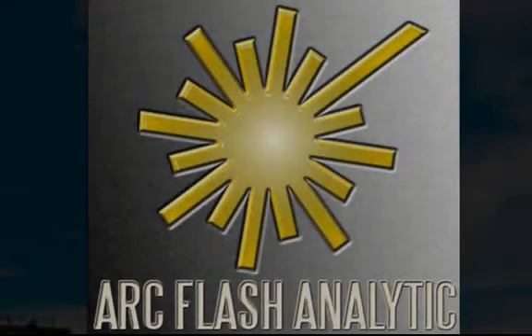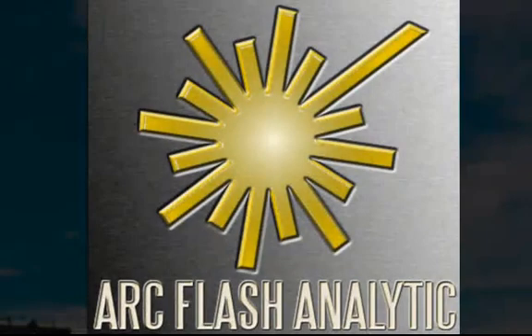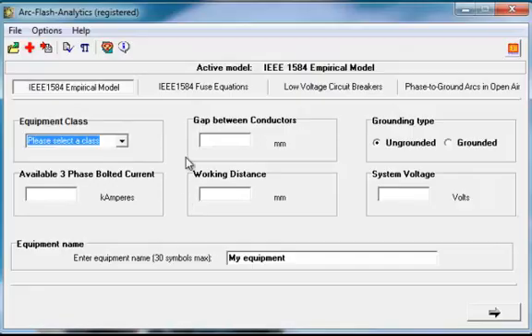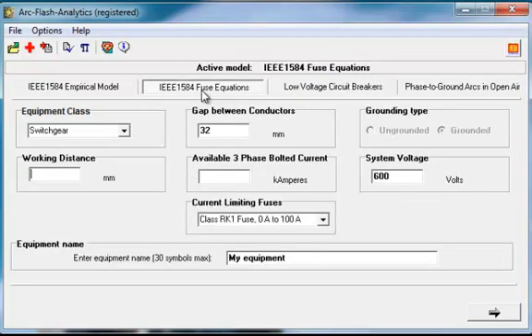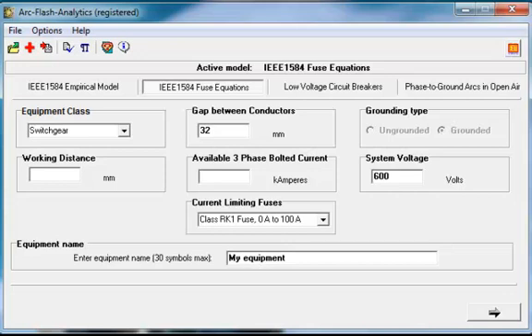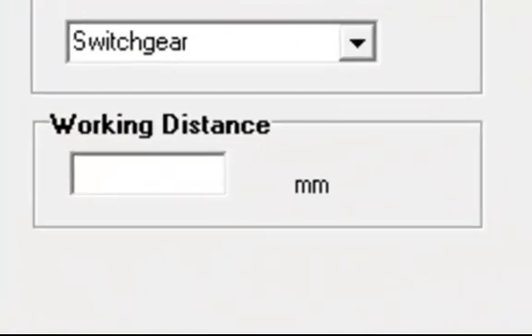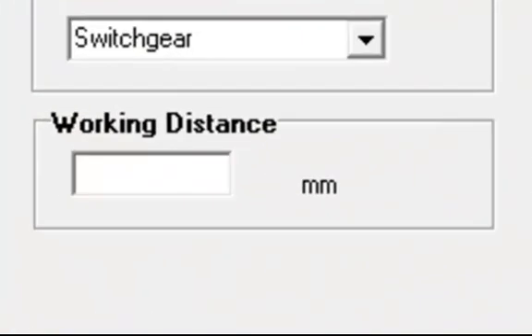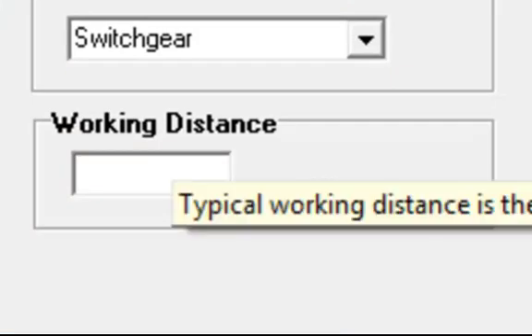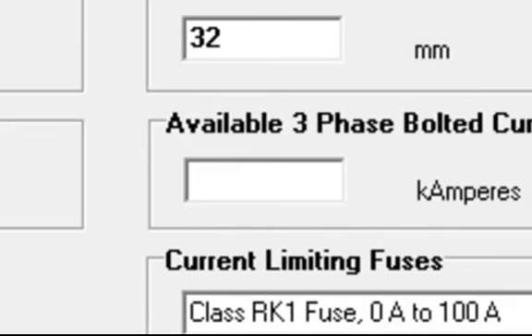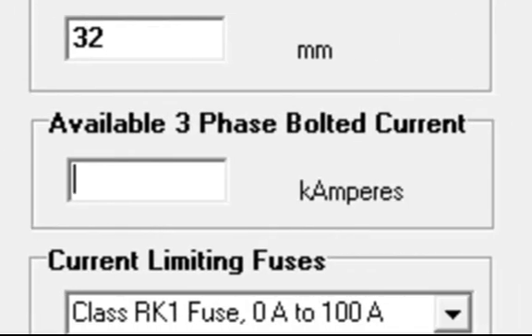Let's consider we have a gear protected by current limiting fuse located upstream. I will show you how to calculate incident energy at working distance, flash protection boundary, and determine personal protective equipment category using ArcFlash Analytic Version 4.1 software. We start with specifying working distance, available three-phase bolted current, and current limiting fuse type from the drop-down list below.